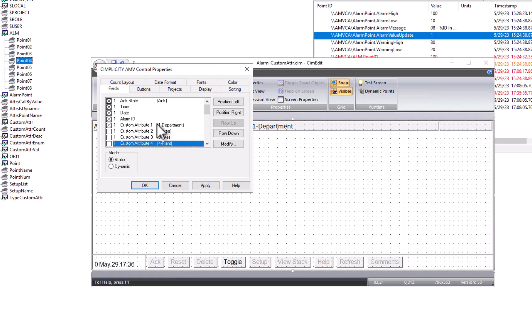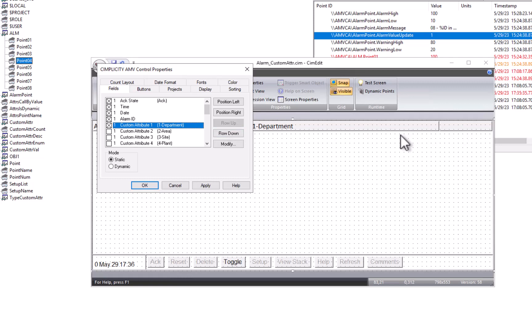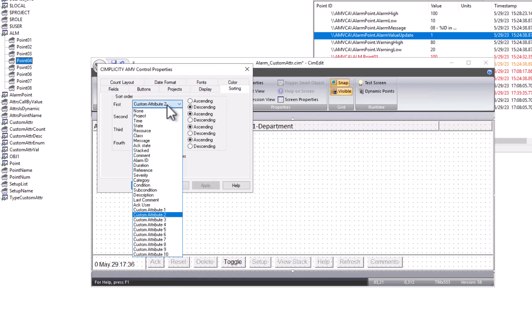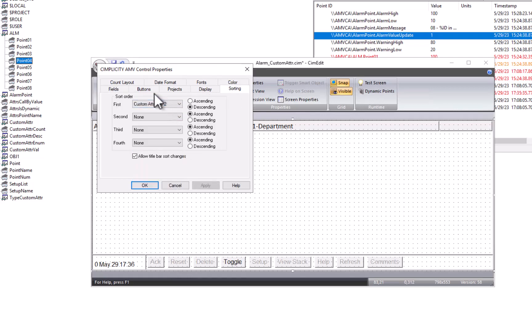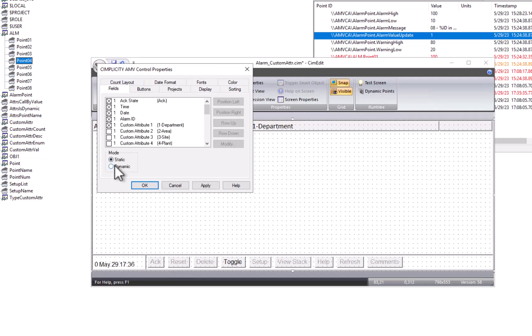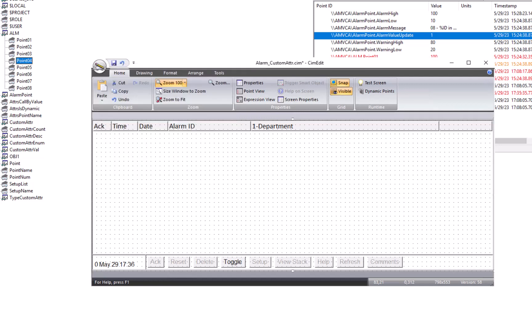So for any given custom attribute, you can give it a name, and you can specify where it lives in terms of the column order or the row order. This will give your operators much more context for the alarms they're looking at. You can sort by different custom attributes, as well as specify different locations for them based on the static or dynamic mode of the alarm viewer.